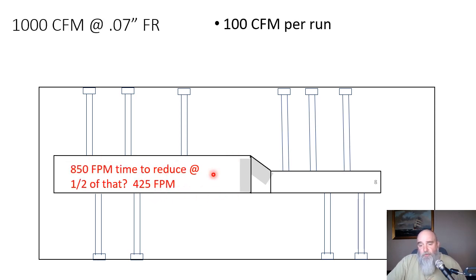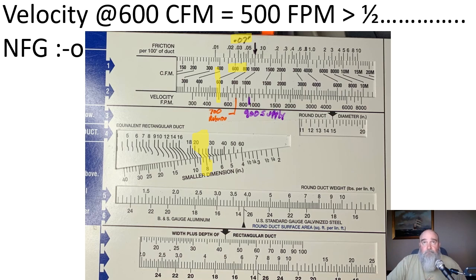When are we supposed to reduce based off of the guidance of Manual D? We haven't reached 24 feet yet, but we have pulled some branch runs off. The first math we're going to do is we pulled four branch runs off. That's leaving 600 CFM of air inside a piece of 24 by 8 ductwork. When we look at our 600 CFM in a piece of 24 by 8 ductwork, it tells me that my velocity is around 500 feet per minute. So is 500 feet per minute less than half of 850?